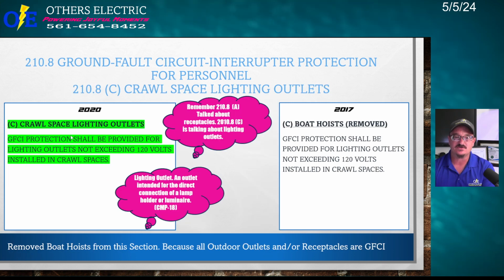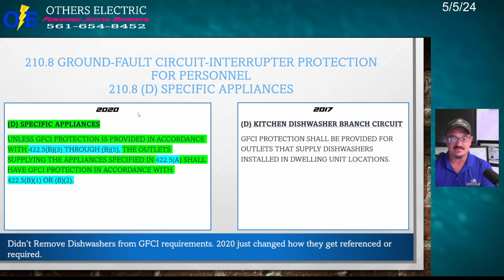So not only do the receptacles in crawl spaces have to be GFCI protected, but the lighting outlets that are 120 volts and less have to be GFI protected. If they're 240 volt, no, only 120 volts or less, not exceeding 120 volts. Okay, so now we've talked about that. That whole thing was added. You got a crawl space, you got a light outlet. What does it need to be? GFI protected. Now 210.8D. Now we're talking about ground fault circuit interruption protection for specific appliances. D, specific appliances. So this whole section changed.